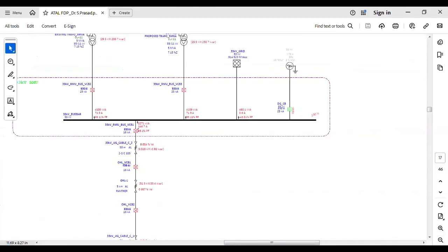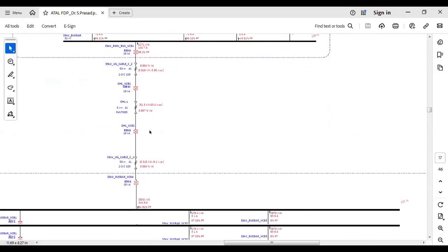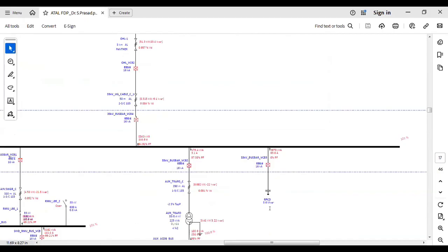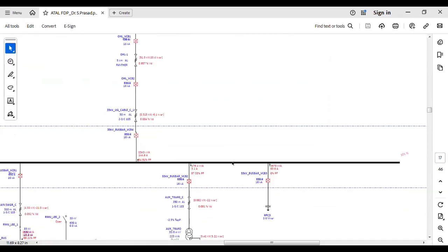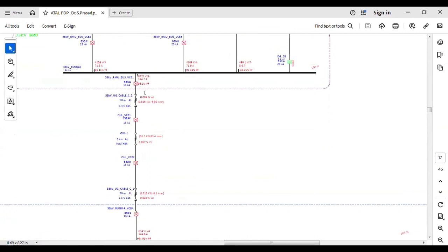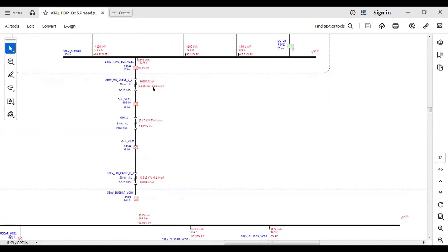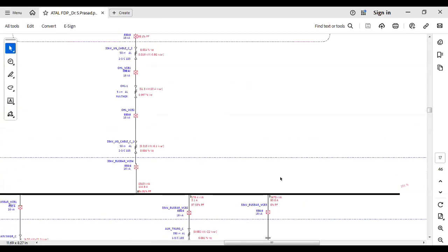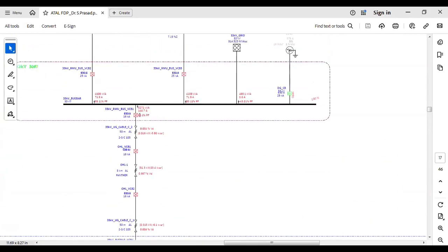You have to maintain 0.95 power factor. You can see here 0.95, 95.1% power factor. That means you have to size the capacitor bank installed at the PV station, the capacitor bank to be connected at the PV substation, so that 0.95 power factor lagging can be maintained. You need to supply reactive power to the grid, and you should not absorb reactive power from the grid, unless instructed by the utilities. So you have to take care of the extreme situations and determine how much reactive power needs to be connected at the PV end so that 0.95 power factor can be maintained at the point of interconnection. That is the task performed by the power engineer.